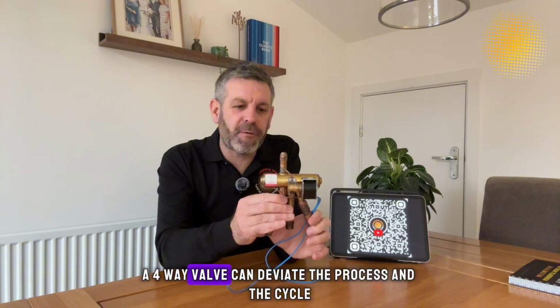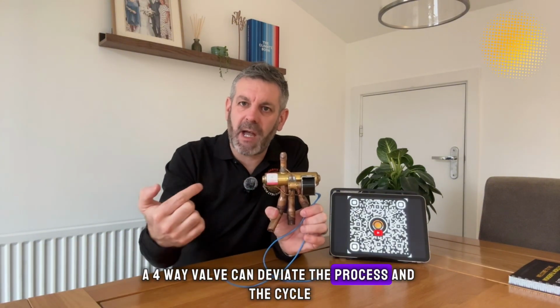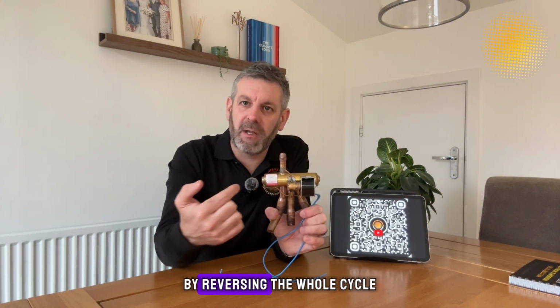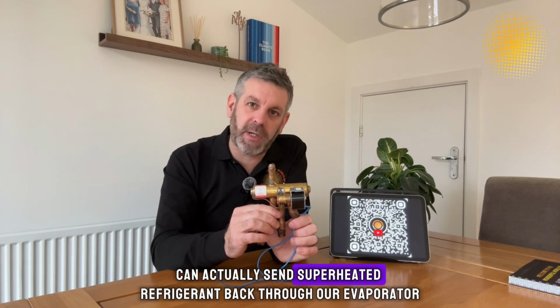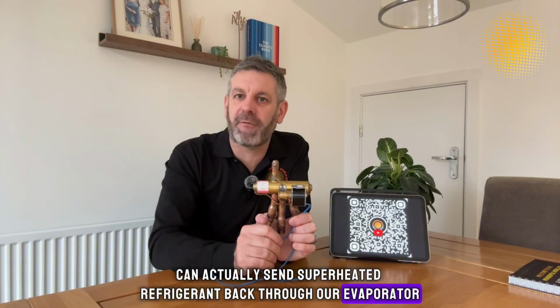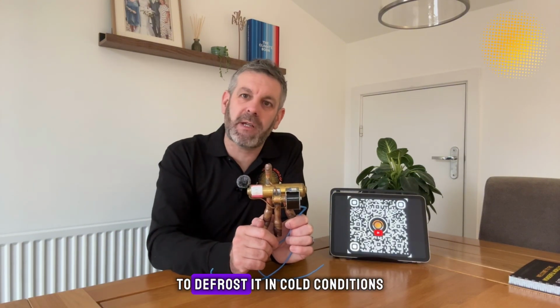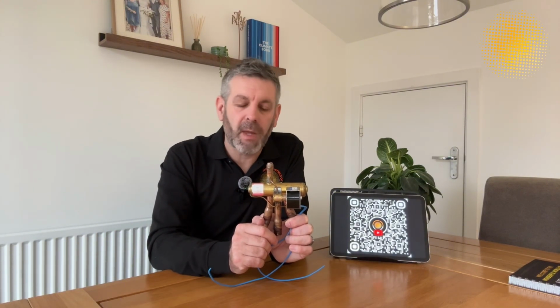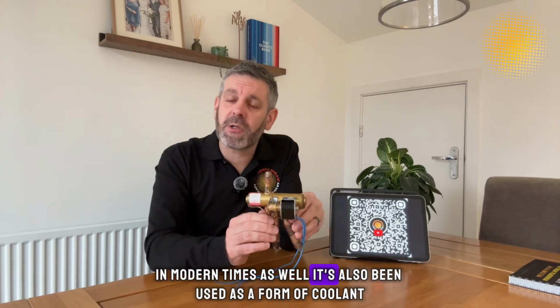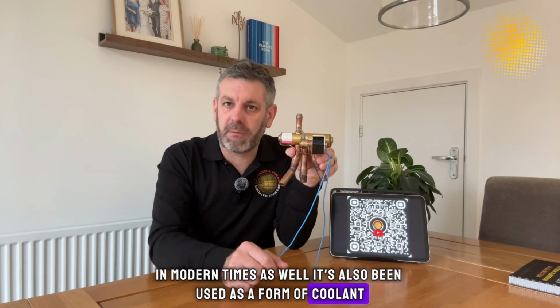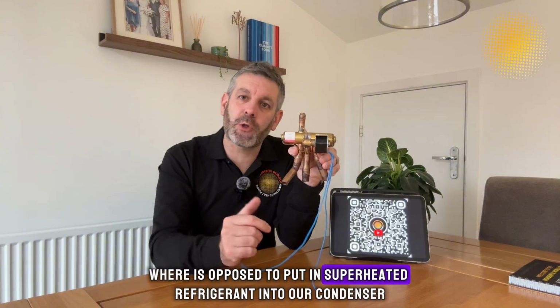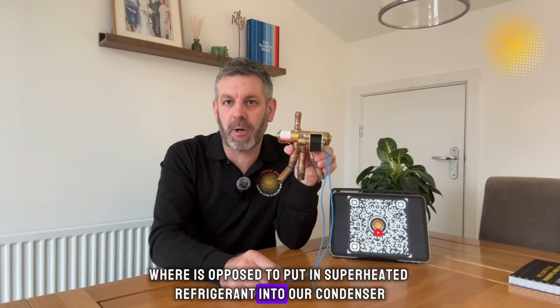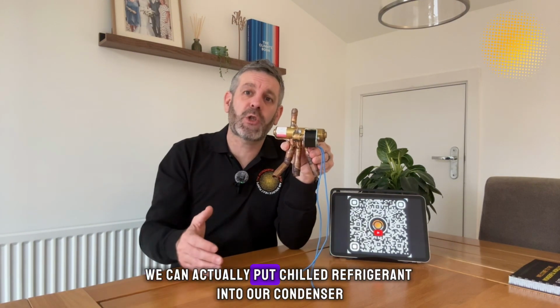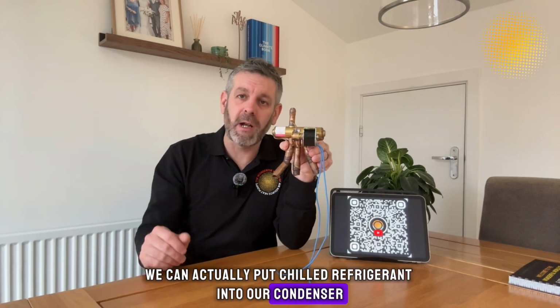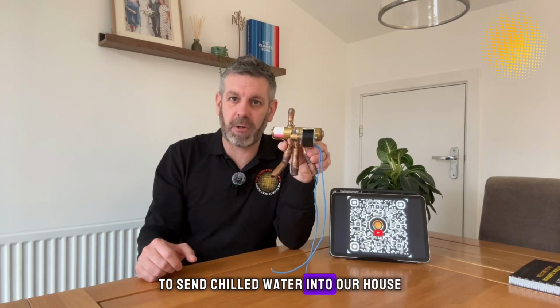A 4-way valve can deviate the process by reversing the whole cycle. It can actually send superheated refrigerant back through our evaporator to defrost it in cold conditions. In modern times, it's also been used as a form of cooling, where as opposed to putting superheated refrigerant into our condenser, we can actually put chilled refrigerant into our condenser to send chilled water into our house.